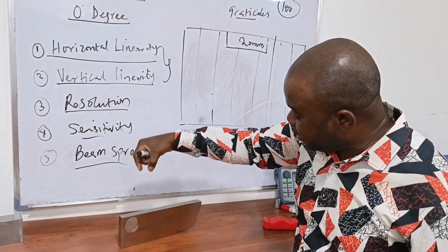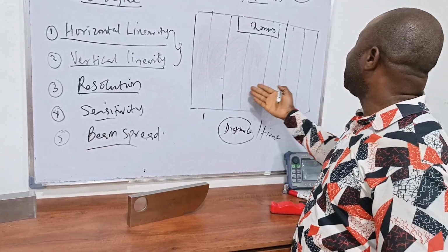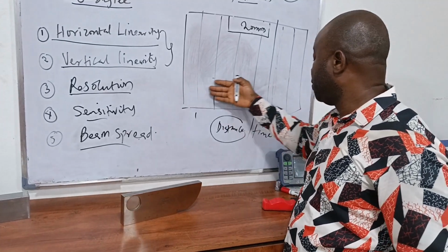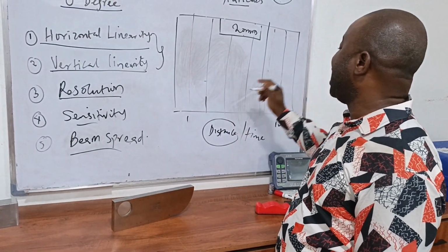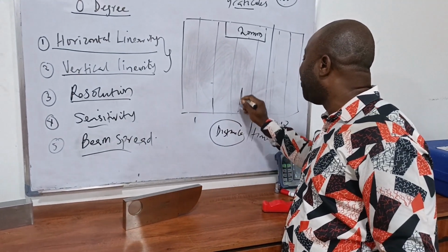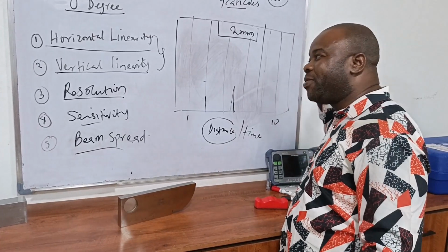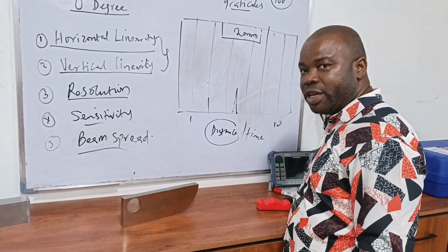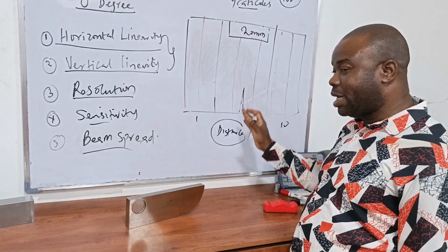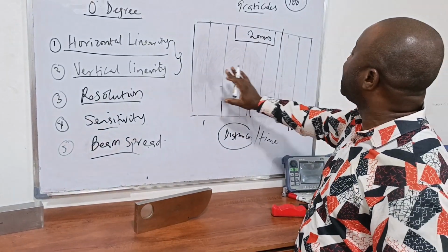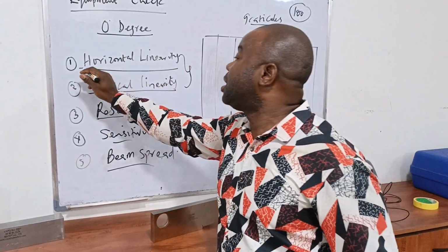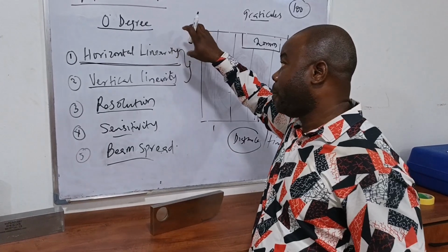I'm using this V1 block, it means that there are going to be 4 echoes that are going to come out. And the first one should be at 25. The second one should be at 50, all the way to 100, if the equipment is calibrated properly. If the machine is able to do that accurately, it means that the horizontal linearity of that machine is okay.